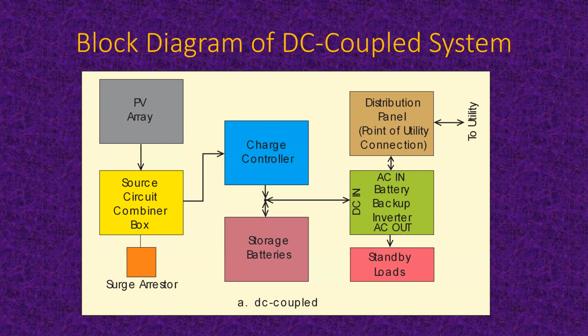Here's a block diagram of a DC coupled system. It starts with the PV array in that gray box in the upper left-hand corner. And this is one of the old systems. This is basically the components of a single box of one of the new systems, with the exception of the storage batteries that are always in another box. And the standby loads are oftentimes in a standby load panel. But in any case, we have the array up on the roof.